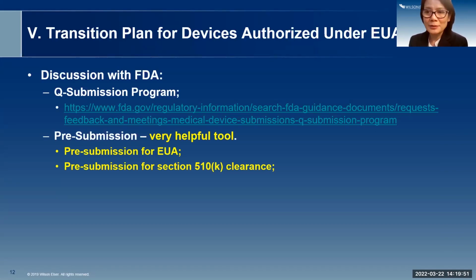And pre-submission is also encouraged. Pre-submission is a very helpful tool for you to test the water. You can submit a pre-submission before your EUA submission or before your 510(k) or even a PMA submission. If there are any issues that you're not so certain about, you can ask for the FDA's input, ask for their comments, and then tailor your final marketing submission toward what the FDA would like for you to include, would like for you to do.